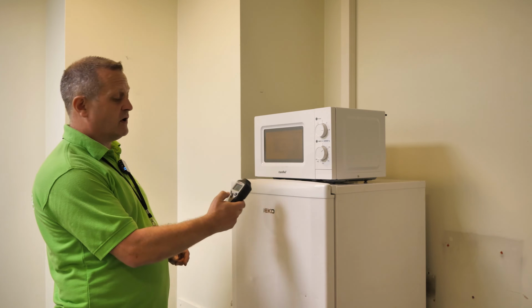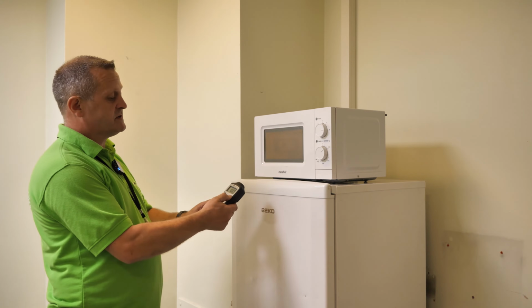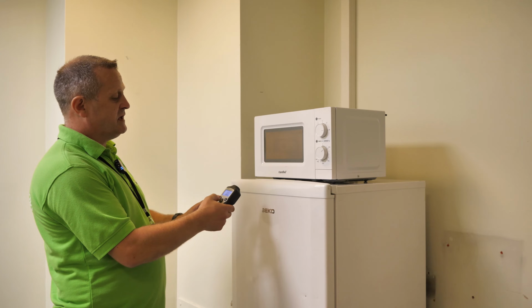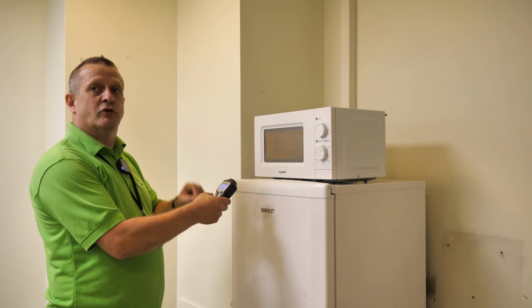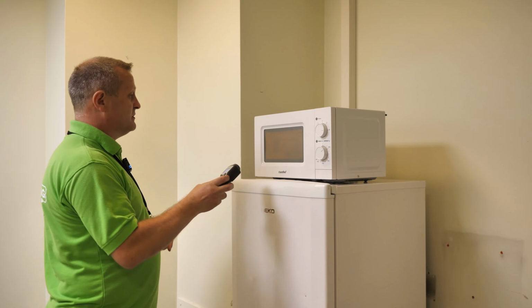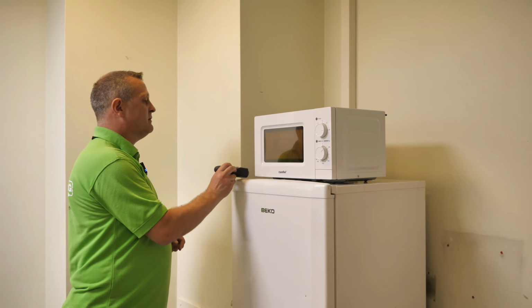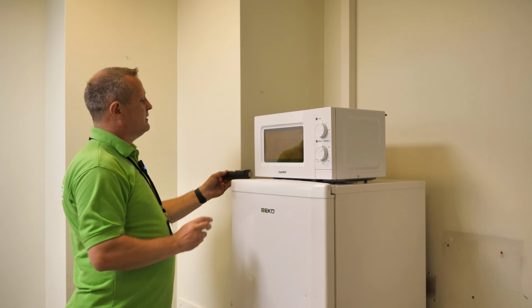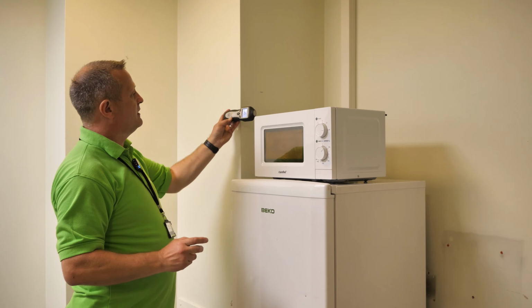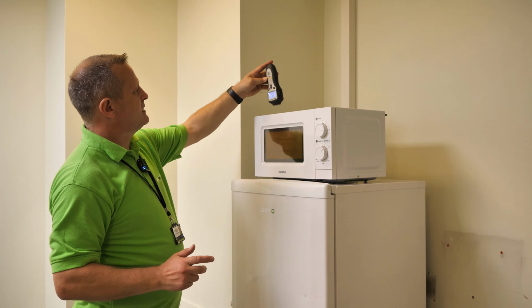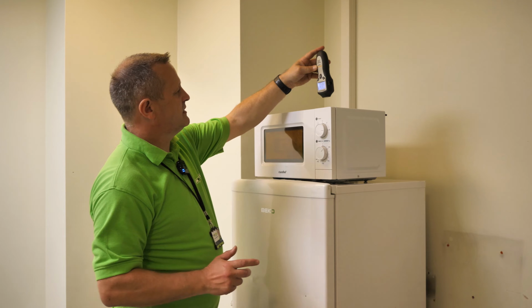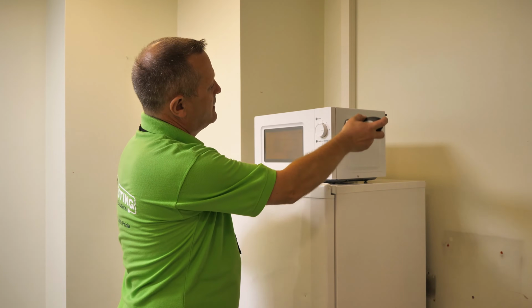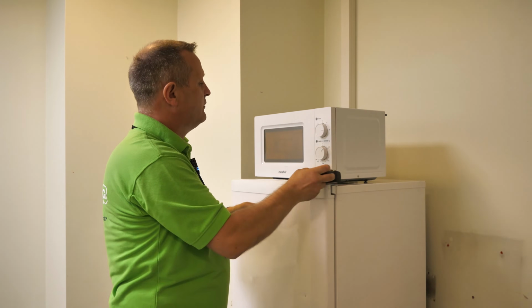We're going to switch on our device and we're going to zero it, and then we're going to press the max button because that will then record the reading. So then we'll start to conduct the test by running the device around the microwave. There'll be some emissions whilst it takes its different readings. Go all the way around.